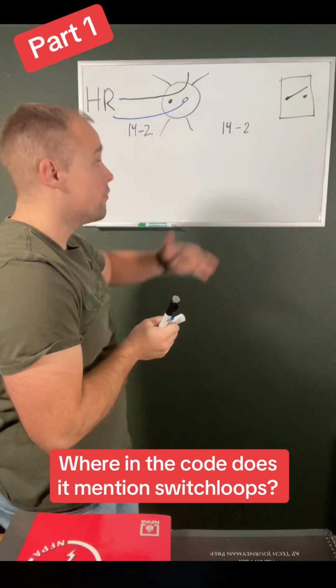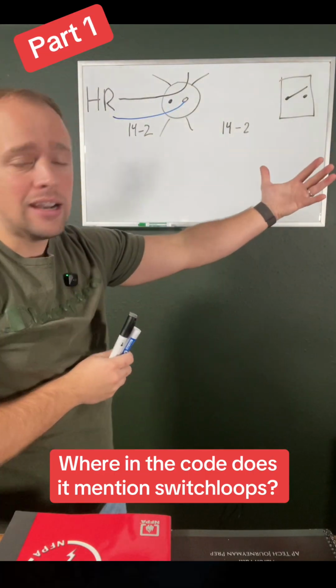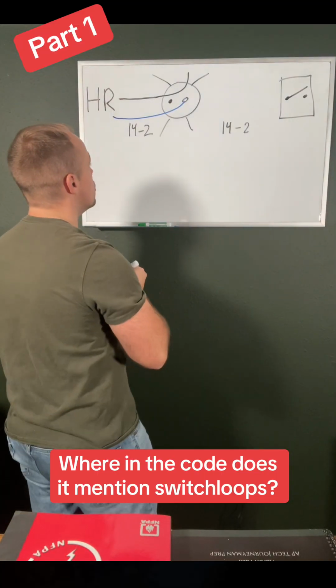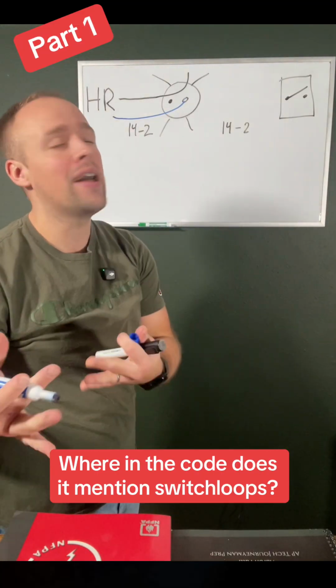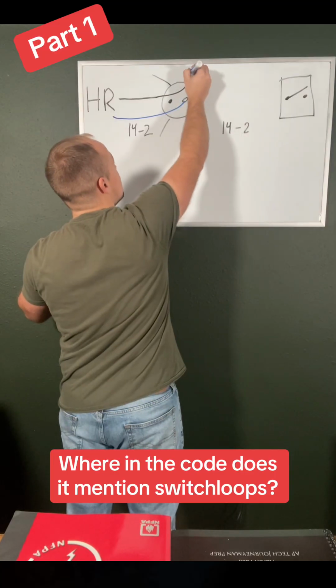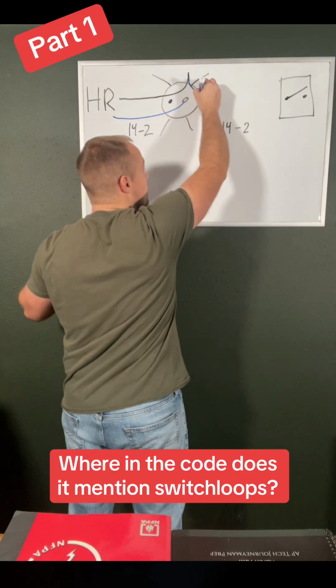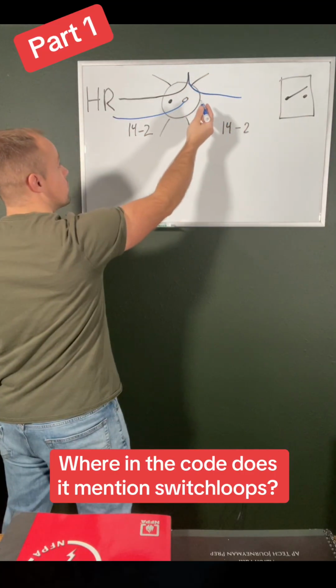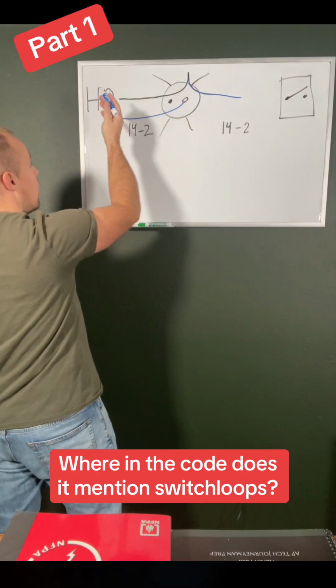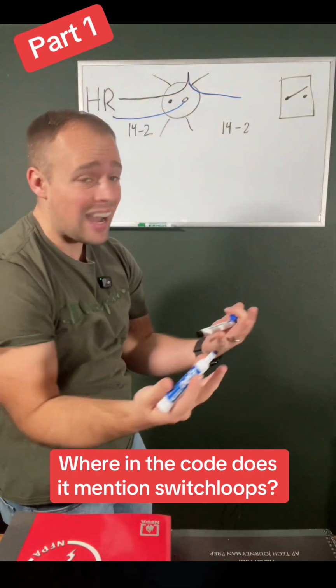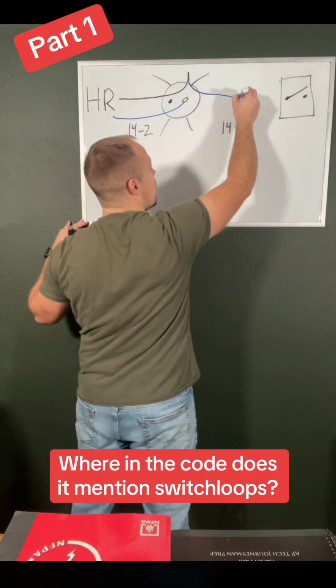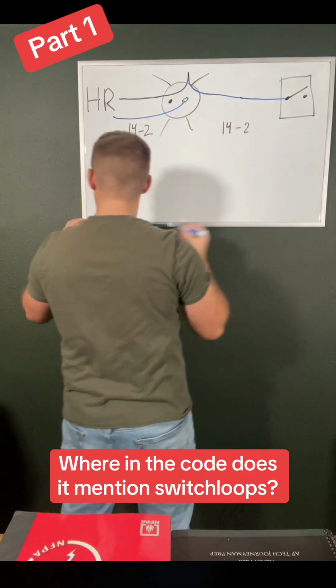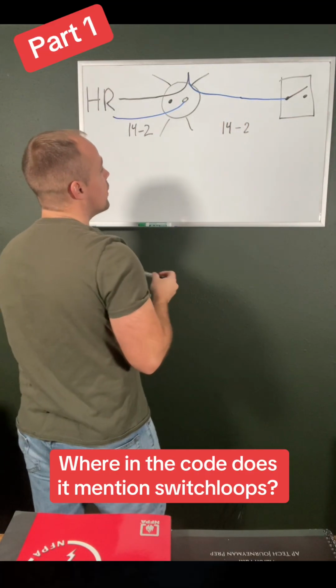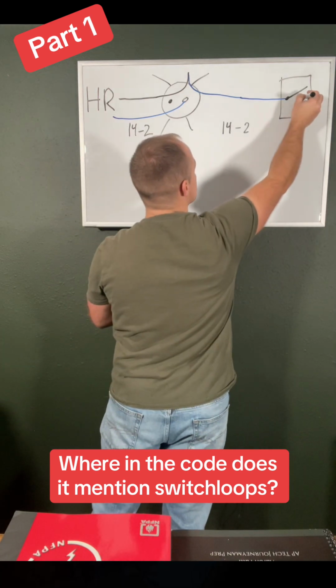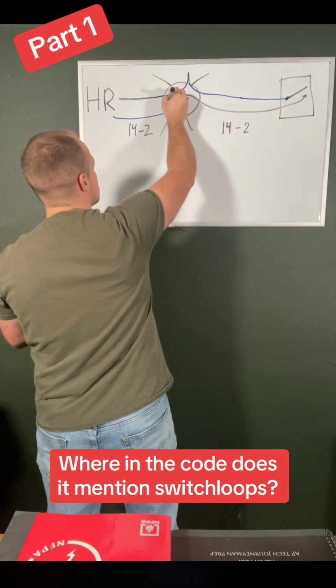So now, again, 14-2 here, we have a black conductor and a white conductor. And what we're going to do, with a proper code compliant switch loop application, we're going to take the white conductor, okay? So it is spliced to the ungrounded conductor from the source, so it's hot, right? It's going to go to my switch. And then from my switch, I'm going to utilize that black conductor of the same 14-2, and it's going to go to the brass terminal of my light.